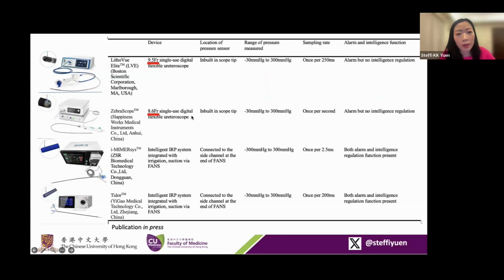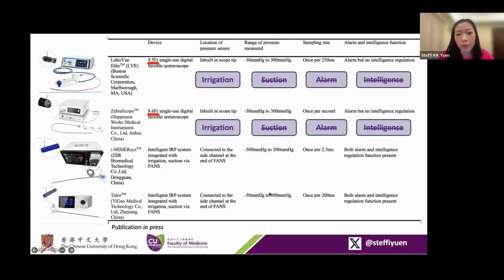So just now we mentioned, is it possible to build these sensors into smaller scopes? The answer is yes, there are quite a number of scopes that are smaller with the inbuilt sensor chip at the scope tip. The range of pressure is ranging from -30 or even -300 for the other systems, but in the scopes it is from -30 up to 300 millimeters of mercury. They have different sampling rates. They do have alarm, but there are no intelligent systems. So these scopes allow irrigation via the working channels, but there's no suction, no alarm.